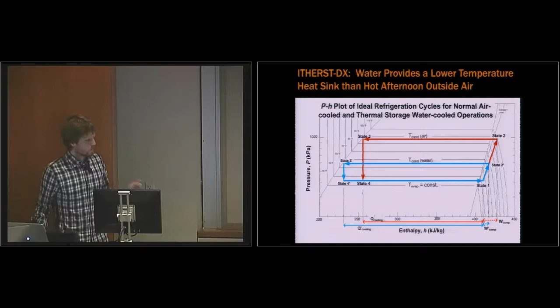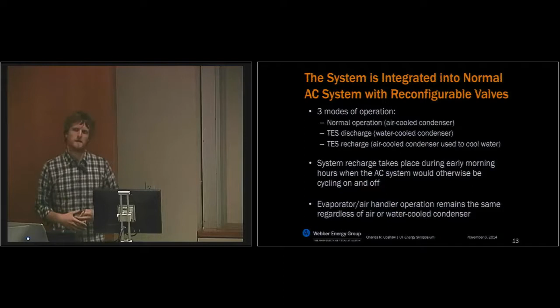So there are three modes of operation: the normal air-cooled mode, the discharge mode, and the recharge mode. The discharge mode is on peak from 3 to 7 p.m., and then the recharge starts at midnight and runs until the system's done cooling back down to its original temperature. And then the normal operation is all the time in between those two. I'm assuming in my model that the temperature in the evaporator is the same regardless of whether you're using the water-cooled condenser or the air-cooled one. And I'm using a tank temperature range of 60 degrees Fahrenheit to 75 degrees Fahrenheit, in case you were wondering.